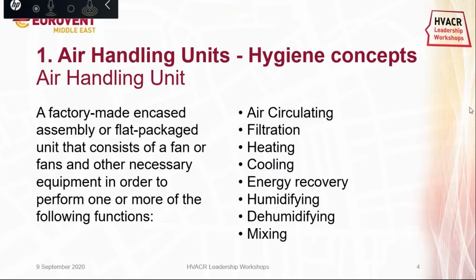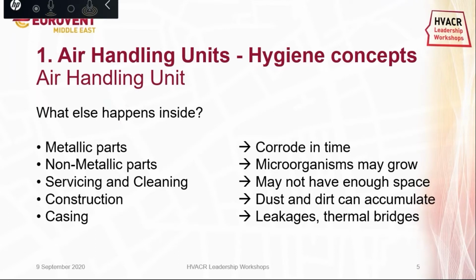Okay, this is the definition of AHU according to Eurovent. It's a device suitable to be used with ductwork while performing one or more of these functions: air circulating, filtration, very important, especially in these times, as I explained before, heating, cooling, energy recovery, humidifying, dehumidifying, and mixing. Okay, but what else happens in an air handling unit in time?